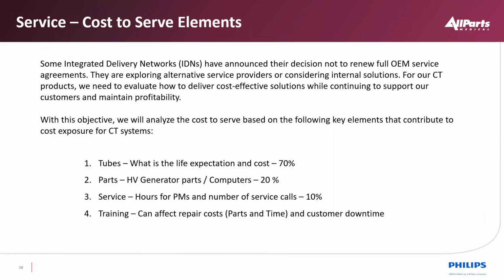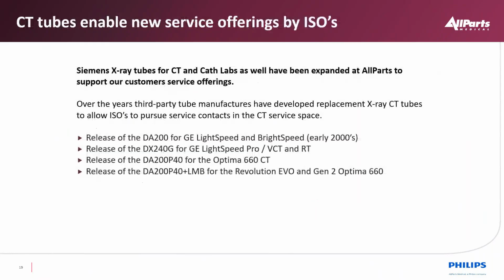And then to support the X-ray tube, we have to create high voltage. So high voltage parts like high voltage tanks, inverters that drive that, and then the computers that support the process. That's about 20% of our cost to serve. And then we have service, the labor part that we provide ourselves, which is service personnel. We have PMs that we have to do, and then emergency service calls.